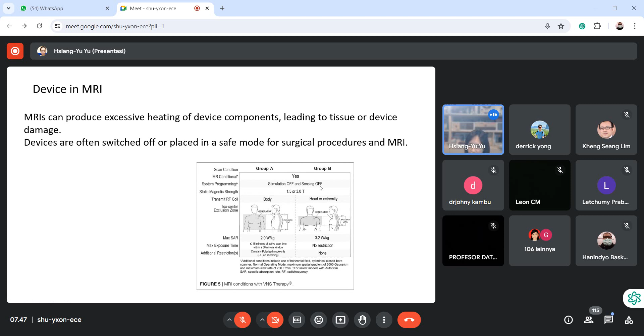For the VNS, for body coil and head or extremity, all this gray zone, you cannot arrange the MRI, the coil cannot cover this area. So there is some limitation for the VNS. But for DBS, you can change to MRI mode or turn it off. The condition is not as strict as with VNS. We can do some body coil and head or extremity scans, not like the VNS. But if you are not so sure, you can just call the representative of the device company. They will give you some assistance.